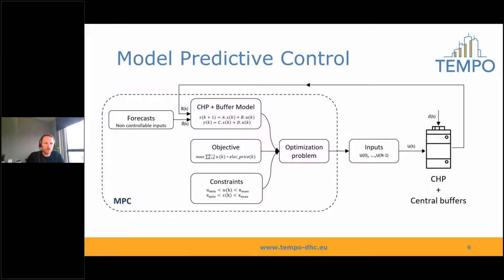Here you can see an overview of the model predictive control approach that we've used in Windsbach. As the name already implies, it uses a model, which you can see here: the CHP and a buffer model. In this system, we use a linear model of the central buffers. We are going to use the flexibility available in the central buffers to store the heat when the CHP is running. One of the important inputs for this model are the forecasts of the non-controllable inputs. The non-controllable inputs are the total heat load of the network, which we forecast based on an outdoor temperature forecast from the Norwegian Weather Service. Then we also forecast the heat that comes into the system from the waste heat plant, and the heat that goes out of the system to the waste heat plant, because that's also possible.